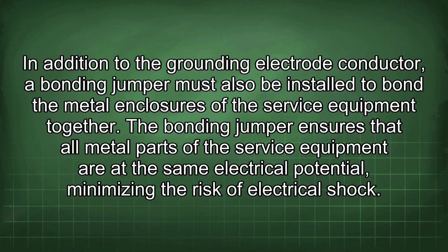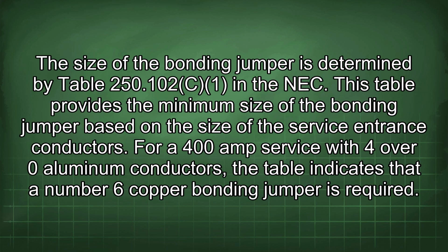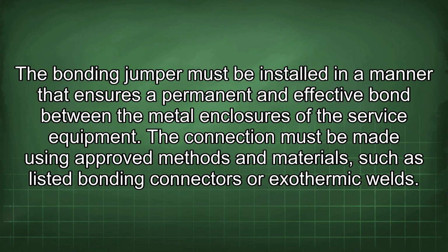The bonding jumper ensures that all metal parts of the service equipment are at the same electrical potential, minimizing the risk of electrical shock. The size of the bonding jumper is determined by Table 250.102(C) in the NEC. This table provides the minimum size of the bonding jumper based on the size of the service entrance conductors. For a 400 amp service with 4/0 aluminum conductors, the table indicates that a number 6 copper bonding jumper is required. The bonding jumper must be installed in a manner that ensures a permanent and effective bond between the metal enclosures of the service equipment.